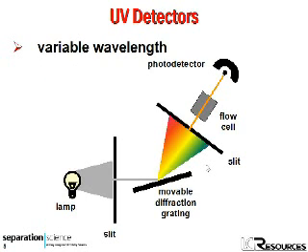Slide 5 shows a schematic of the variable wavelength UV detector. This is one of the two most popular LC detectors in use today. It's quite simple in concept and very reliable. The presence of a sample component in the column effluent is measured by the change in UV absorbance in the mobile phase as it passes through a flow cell.